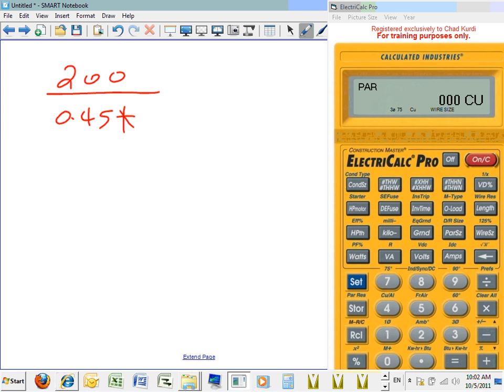Next, the temperature. What was my temperature? The temperature was 60. Only a fool will do these two at the same time, but we're going to do it anyway. 60. What is the derating factor for 60? Everybody came up with 0.71? Derating factor. This is from 310.15(B)(2)(a). Yes, no? 60, you're under the 90-degree column? Come on, somebody. 0.71? 0.71. Okay. Where's your calculator?